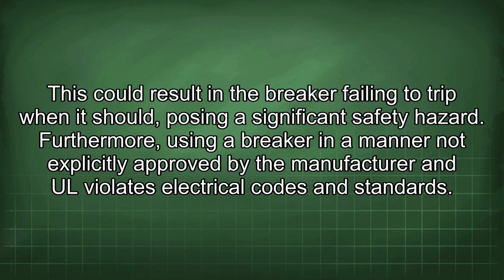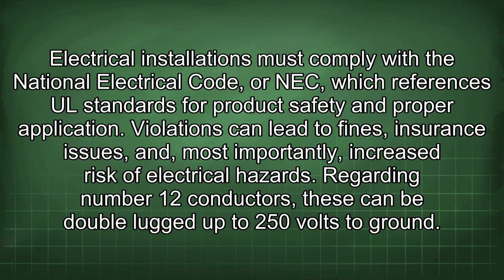Furthermore, using a breaker in a manner not explicitly approved by the manufacturer and UL violates electrical codes and standards. Electrical installations must comply with the National Electrical Code, or NEC, which references UL standards for product safety and proper application. Violations can lead to fines, insurance issues, and, most importantly, increased risk of electrical hazards.